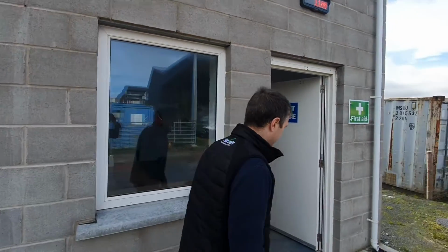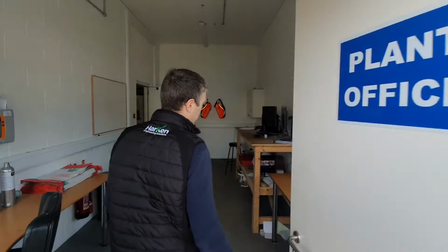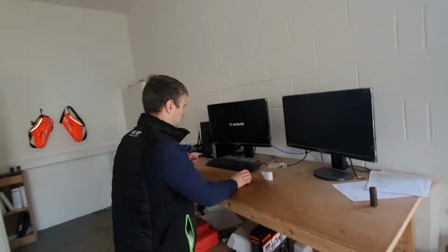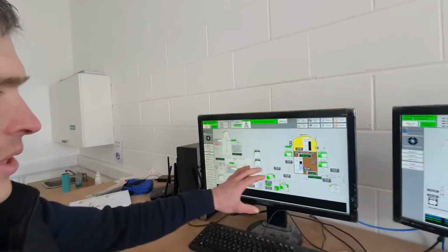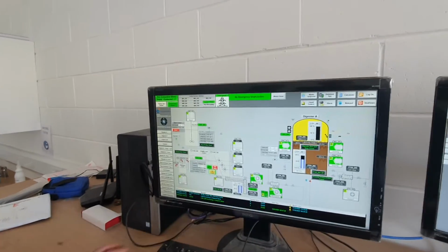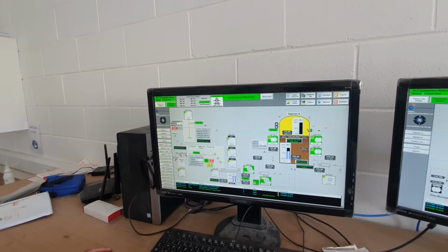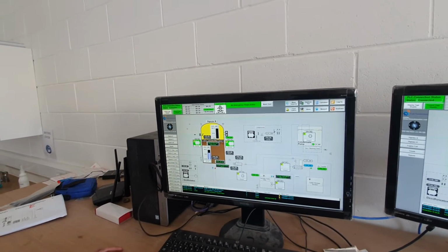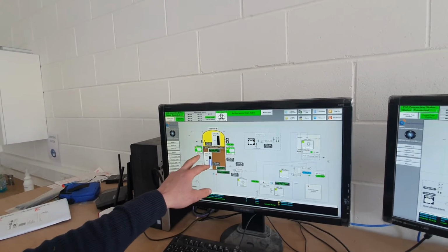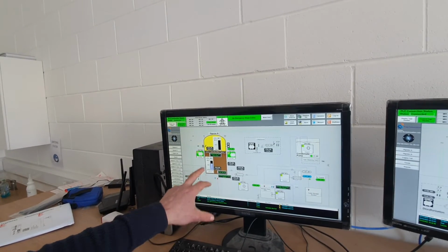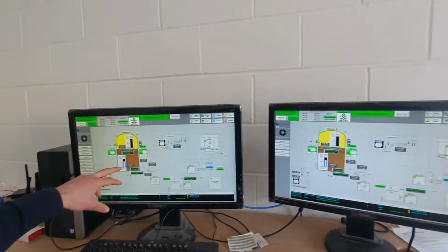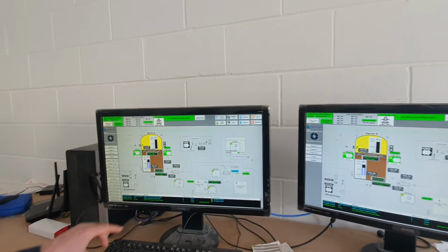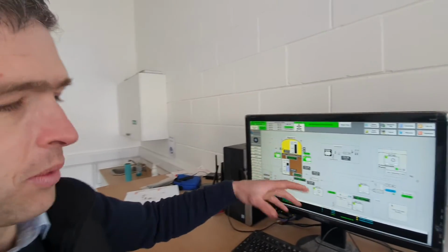Okay. This is your plant room in here, is it? This is the control room. You can see the functions of everything here: our primary digester, where the feed sequence goes in, and our different motors and pumps. The secondary, the post digester, we can see our two mixers here and the amps that they're taking. The temperature of this is at 49.9 degrees. The height of the digester unit is recorded, and we keep the mixers going based on the amps, so based on how dry or how wet and liquefied the material is.